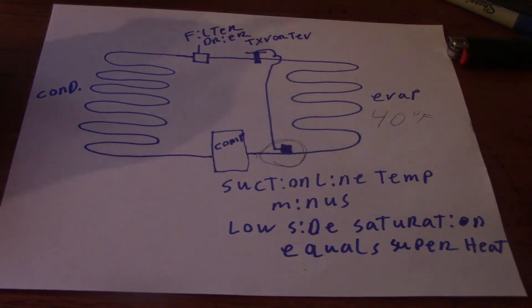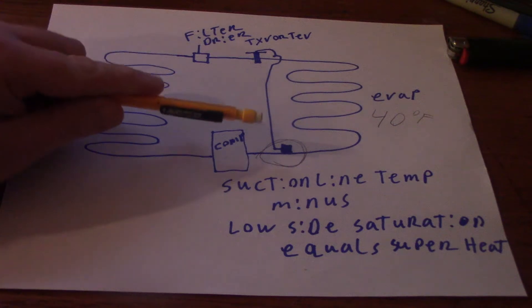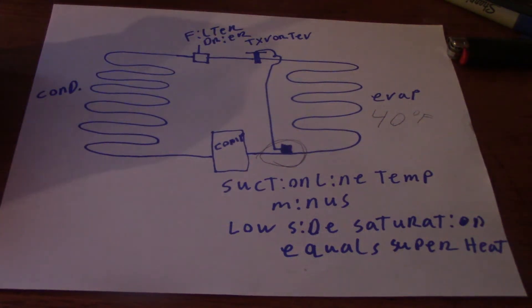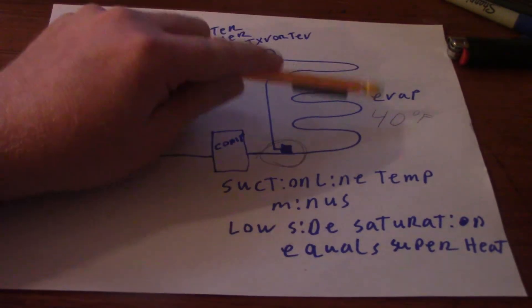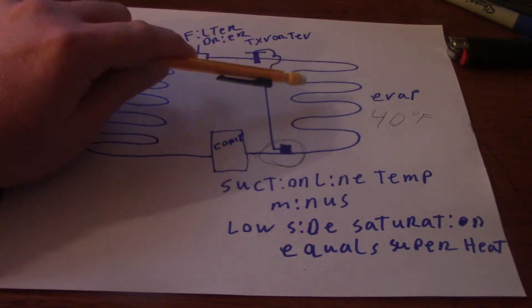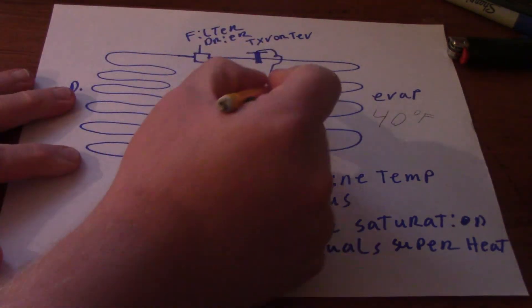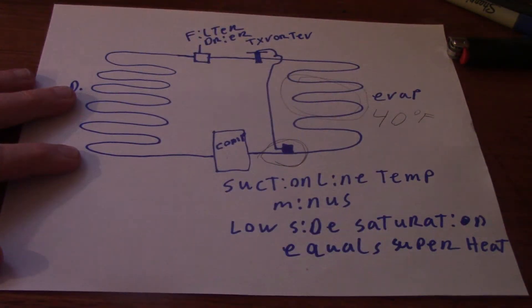If it was like R134A with about 15 PSI, you're talking roughly 15, 16 degrees saturation temperature. What that saturation is, the temperature of the refrigerant right there in the evaporator, that's the temperature that's boiling off. You have your liquid and vapor mixture there.